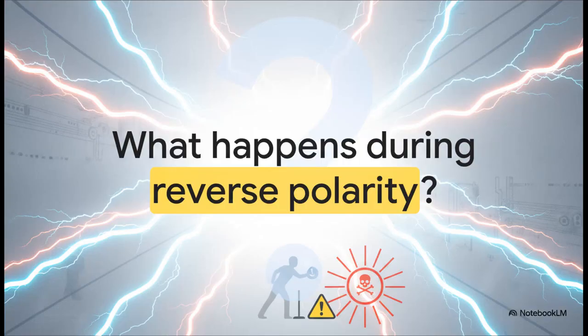Okay, let's dive right into this. Have you ever paused to think about the absolute worst-case scenario when a system is energized with reverse polarity? I mean, the stakes literally could not be higher. One simple transposition of conductors means the entire earthing system of an installation could become a live deadly hazard. We're talking fatal consequences for anyone who touches those earthed conductive parts.